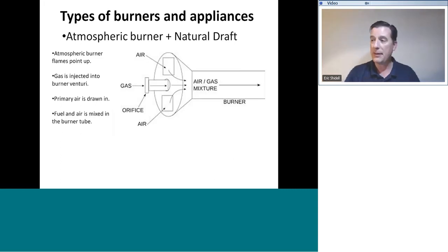So while we're here, let's talk about that Venturi effect. This is how natural or atmospheric burners work. It's called atmospheric because the whole thing works at essentially atmospheric pressure. Gas is delivered to the burner through an orifice under pressure, under a very small amount of pressure. In fact, for natural gas, the pressure delivered to the orifice is generally 3.5 inches of water column, or roughly half of what the line pressure was, so an eighth of a PSI, very, very small pressure. It's just a whisper.